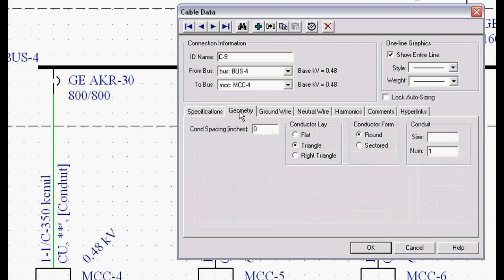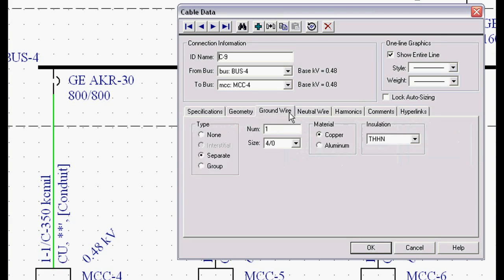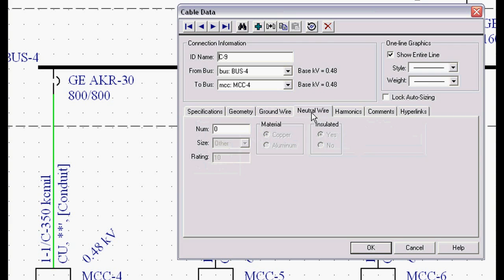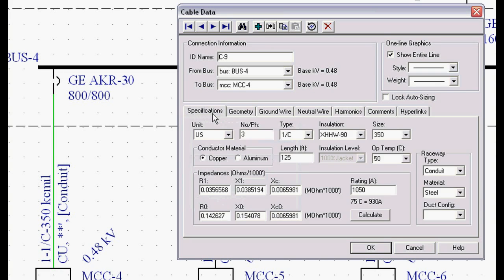Geometry, you can get very fancy and specify different conductor spacing and geometry, whether the conductor is flat lay, triangular, right triangular lay, conduit size and information, ground information, neutral wires, harmonics for everything. It can be very detailed if you choose it to be. For a standard arc flash study, you're only going to fill out the spec tab and that's good enough.